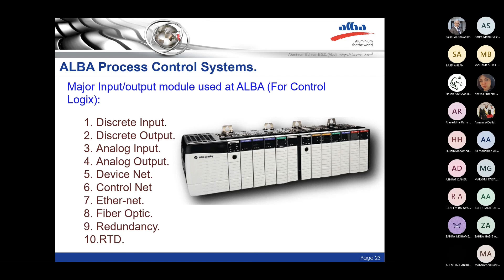RTD is used to measure temperature, resistance temperature detector. Before, we used a transmitter where we connected the probe of the RTD to that transmitter in order to get 4 to 20 milliamp out of that transducer. Now, Rockwell Automation has a card where we can connect the probe directly to that card. We don't need any transmitter or transducer in between to convert the resistance to milliamp. As we said, in ALBA, the main control philosophies we are using are on-off control and PID control, proportional, integral, and derivative control. If you observe from here, the proportional is the green one, while the integral, this is the set value.